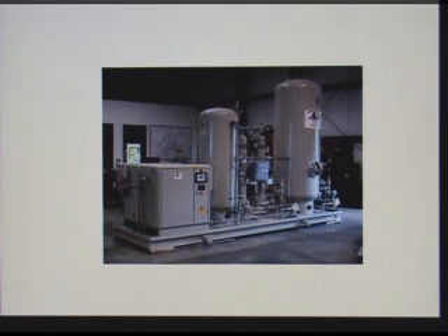I mean, there's an art to it, and then there's a lot of guessing to it in some instances. You look at your P&IDs, you come up with the number of users as far as instrument valves, nitrogen generators, utility requirements, and you can come up with a pretty good estimate of what the overall consumption is going to be. At the start of the job, it is an estimate, and we generally ask that there be a pretty healthy percentage addition onto that, because very few plants have ever required less air as they develop. Usually they all require more.